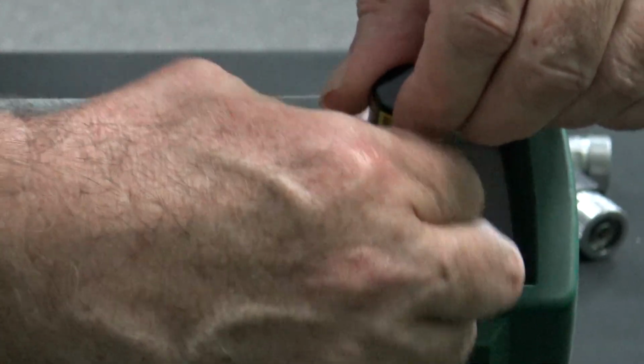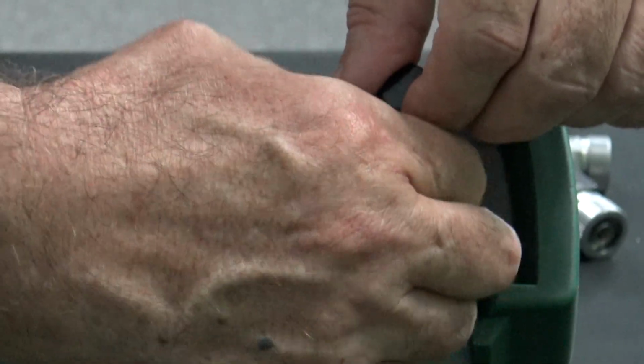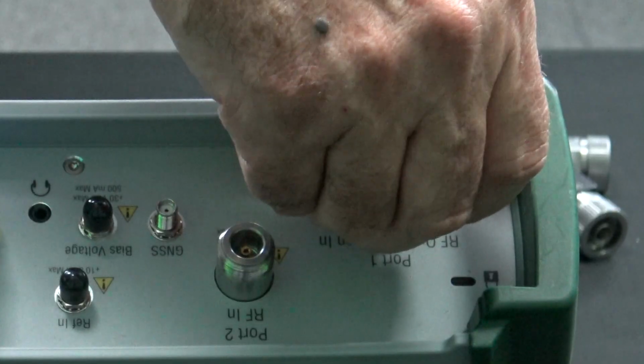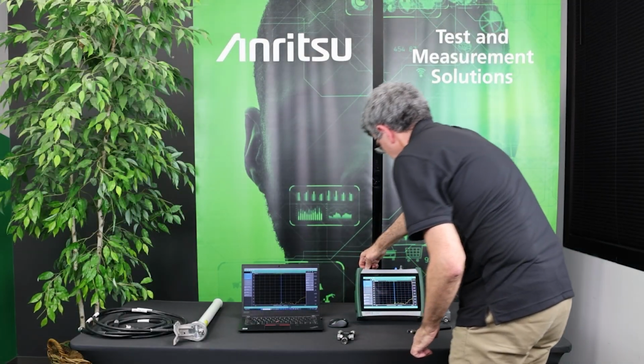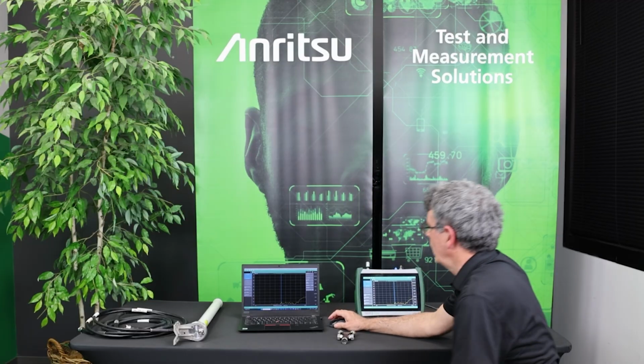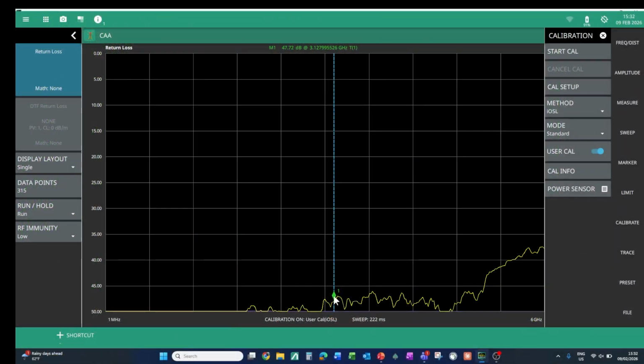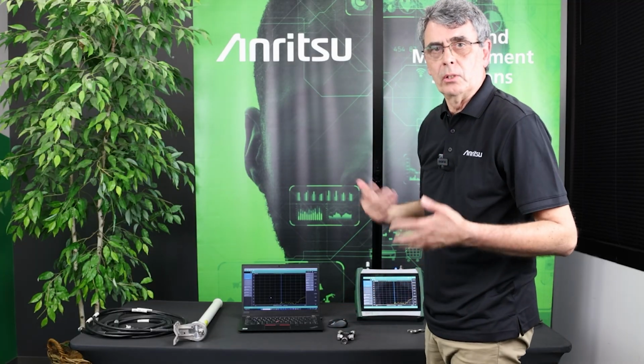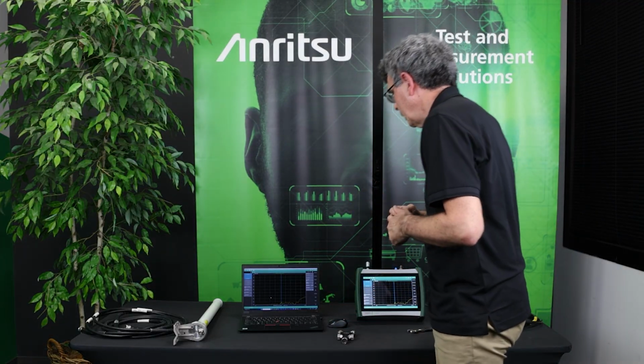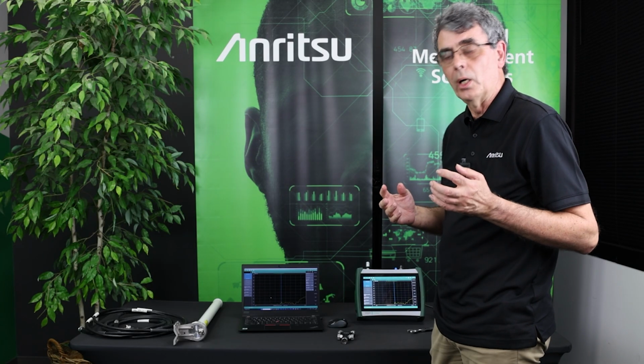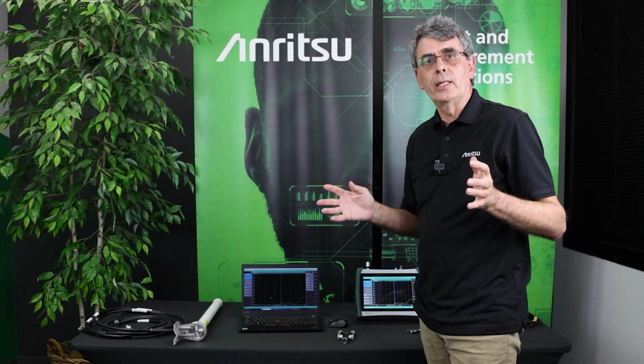Reconnect the precision load. So with the InstaCal, you can see that the dynamic range is a little bit less than for the mechanical cal device, but still better than 45 dB directivity up to 5 gigahertz, just decreasing a little bit as we get up to 6 gigahertz. For most LMR systems and cellular systems, we're working below 4 gigahertz, 4.2 gigahertz, so actually the InstaCal works really well.